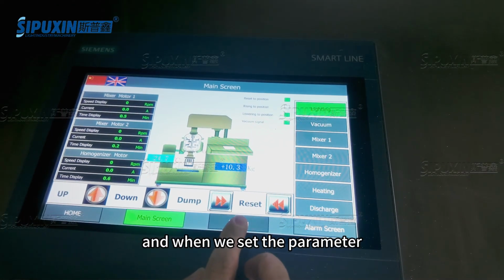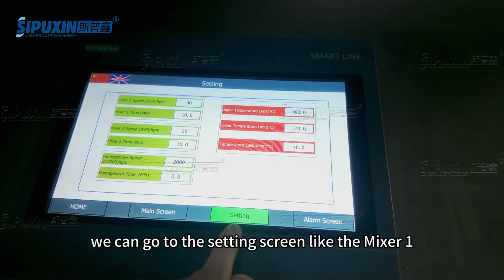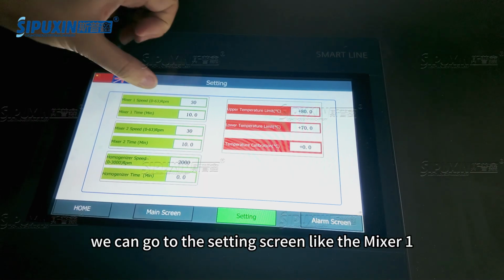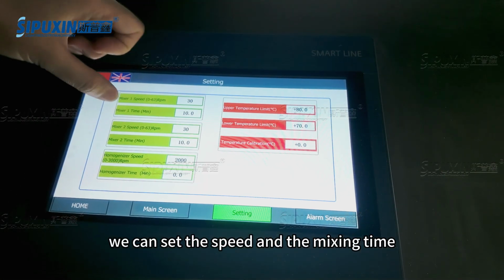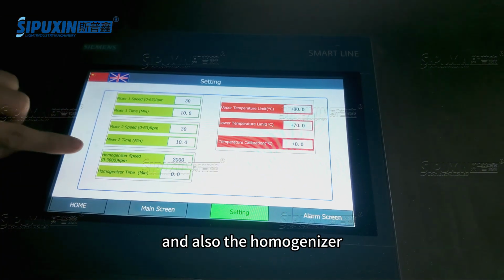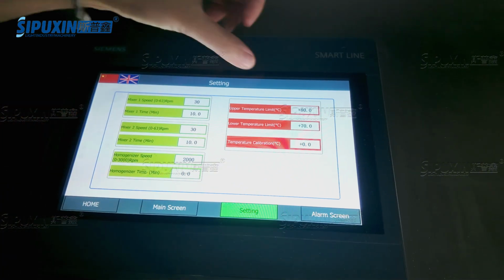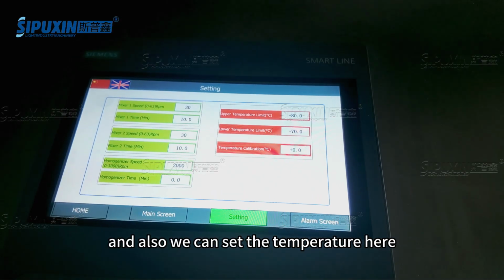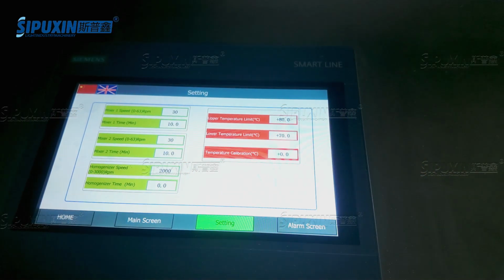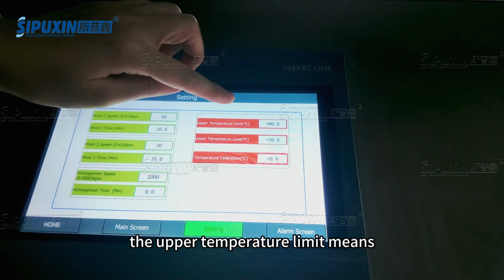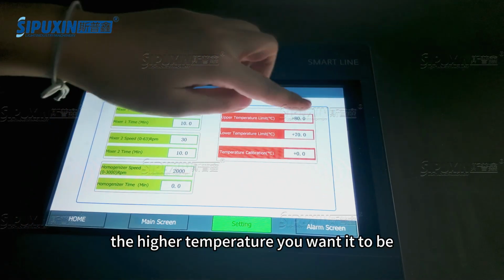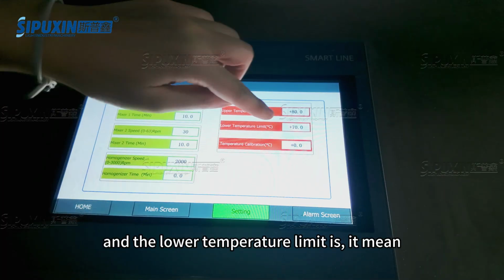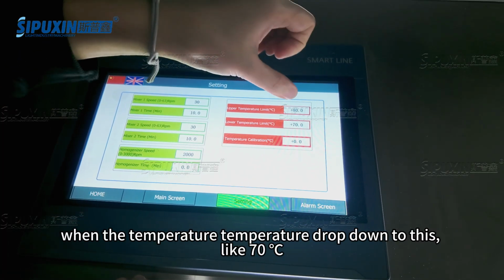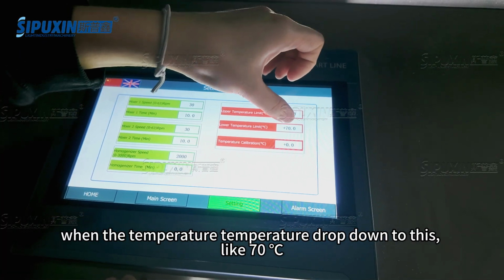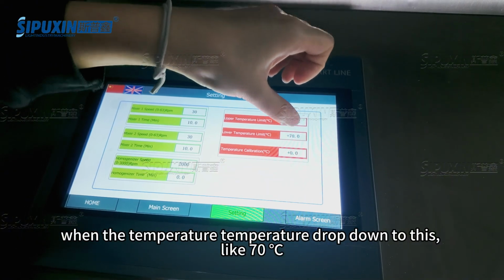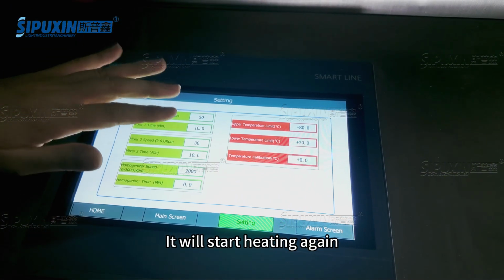When we set the parameters, we go to the setting screen. For the mixer, we can set the speed and mixing time, and also the homogenizer. We can also set the temperature here. The upper temperature limit means the highest temperature you want, and the lower temperature limit means when the temperature drops down to that point, like 70, it will start heating again.